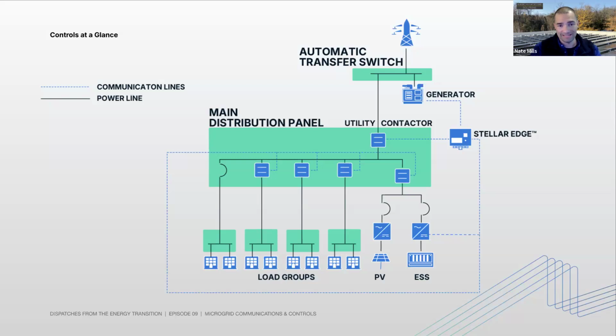If when it does that, it does not see an active grid signal, then it will trip, right? It'll shut down. And so these microgrids are typically fail safe, and by that I mean not feeding power to some unknown condition. So it does depend on having consistent communications with the various components of the microgrid. And I think what he may be pointing out is that rightly, the more of these connections you have, the more potential failures you have. So the more complex the wiring, the more complex the communication, the more chances there are for something to go wrong and for the system to trip offline. One of the things that we build into our systems is some amount of manual backups.